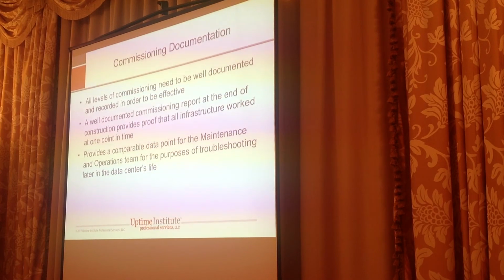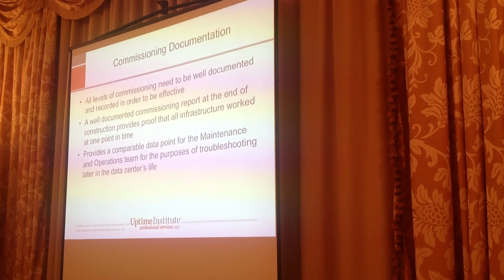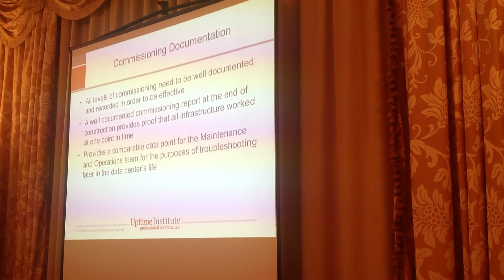Commissioning documentation: all levels of commissioning need to be well documented. This documentation is the data point you have to compare to in the future when you have problems - what were you able to achieve during commissioning, what has changed. This is where you document the standard configuration - as you're doing the testing, you determine what's the standard configuration of everything in your data center. It's a great opportunity to pick up that data.